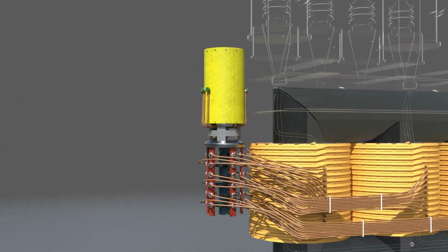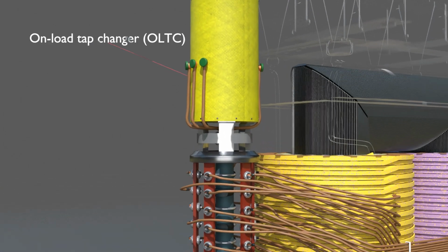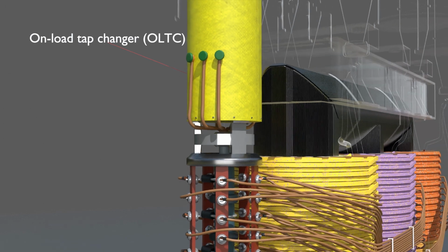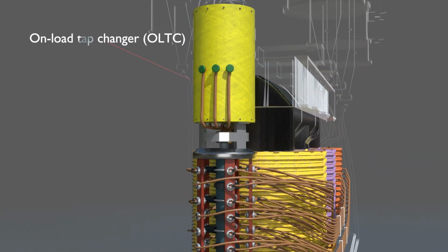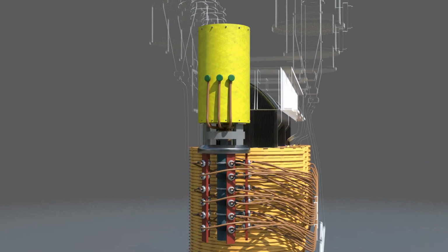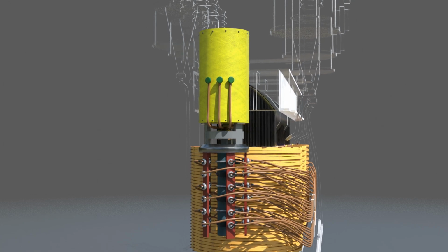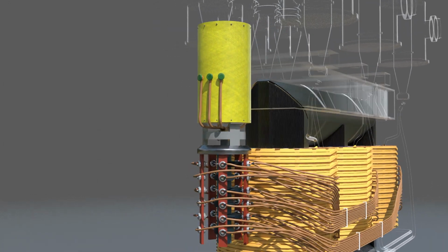Let me tell you about an on-load tap changer. It's a clever device that keeps the voltage steady in a transformer while it's running. How does it do that? Well, it adjusts the number of winding turns to control the voltage, all without ever switching off the power.